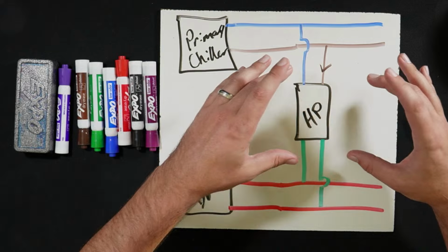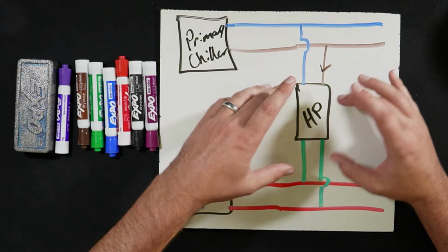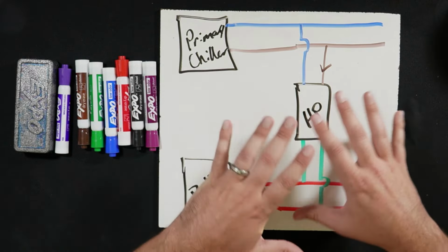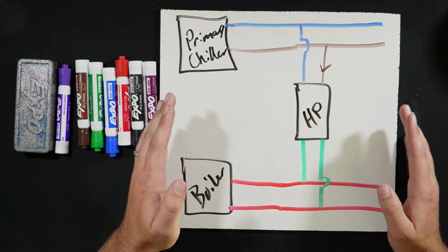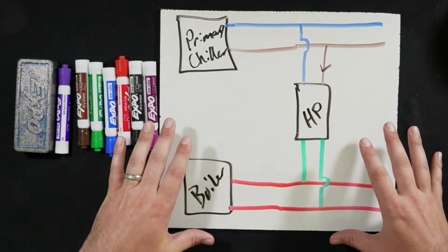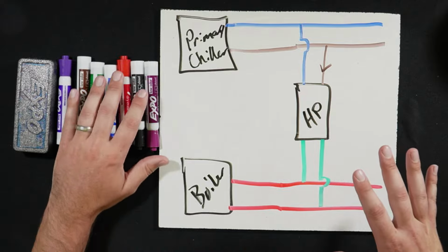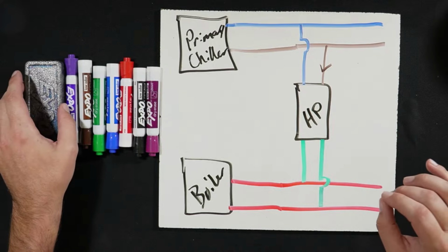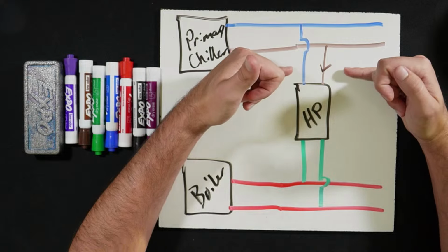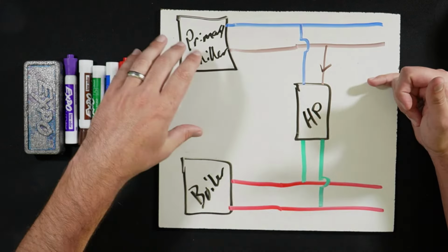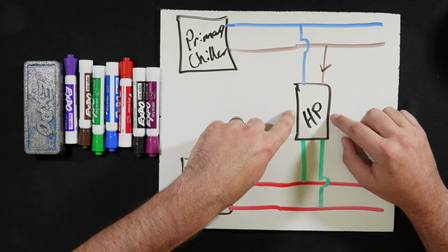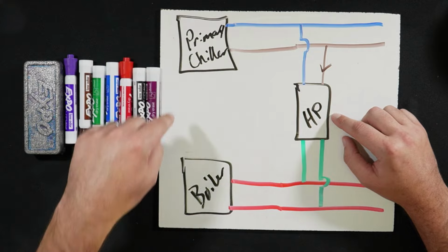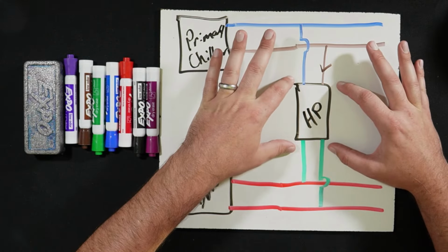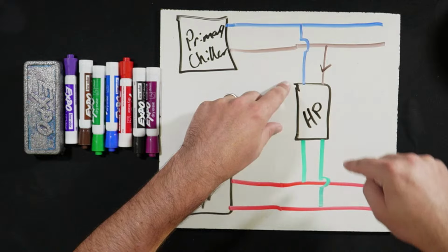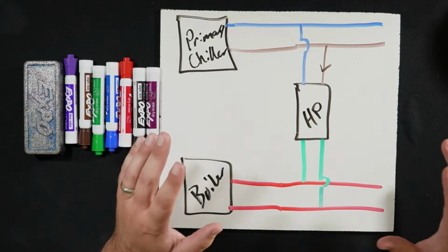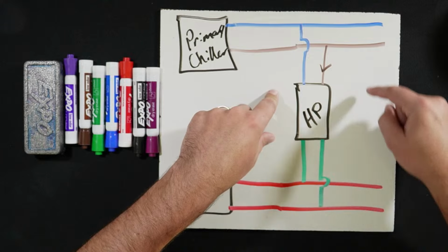So when it comes to the question of how we're simultaneously heating and cooling, this is what I see as being discussed as an industry standard. Now, there are other variations of this. This is not like the set primary, but this is one of the main recommended ways that I'm seeing this pushed right now. There are other configurations, okay? I'm just saying that up front. If you research this or look into it, you will see this done in a few different ways. This is just a more prevalent one, and this is the one I'll focus on to explain the simultaneous aspect of this. These chillers are, from what I've seen, usually not replacing the primary cooling system. It's not replacing the primary heating system. It's usually installed as a supplemental so that we can literally transfer heat out of here into here. It's a type of heat recovery setup. Truly, we're just calling it a heat pump for whatever.